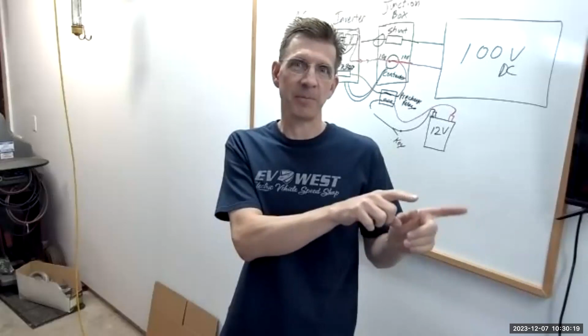The other, and I'm not sure which component you're using, or which tester you have there in front of you, but the other one is a milliohmmeter, and we're using that to see not if the windings are leaking to the case, but if the windings are shorted within the motor winding itself. Essentially you're measuring, in a very accurate way, the resistance of each winding in the motor. So those are kind of your ones. When you're doing just the basic isolation test, you're just using a voltmeter, checking for voltage between the high voltage and the low voltage system. If it fails that test and you determine it's in the motor, then you're going to use the insulation tester for checking leaking from the windings to ground, the case of the motor, or the milliohmmeter for checking if the windings are shorted within themselves.